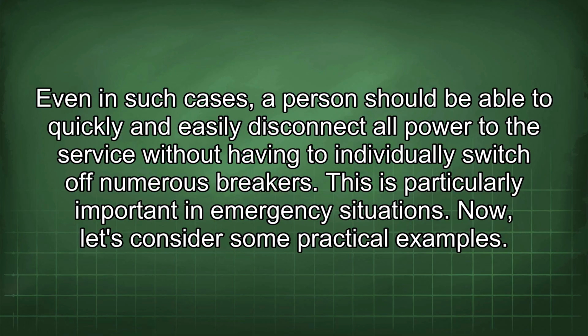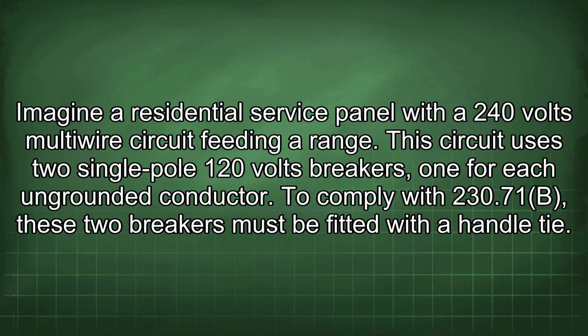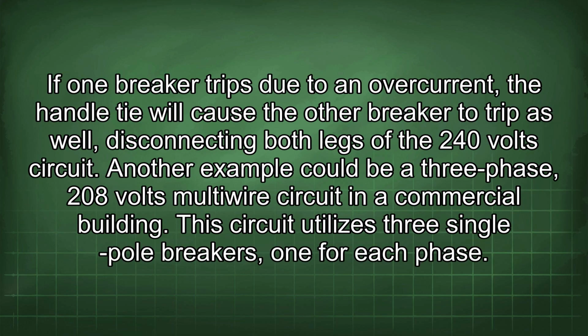Now let's consider some practical examples. Imagine a residential service panel with a 240-volt multi-wire circuit feeding a range. This circuit uses two single-pole 120-volt breakers, one for each ungrounded conductor. To comply with 230.71(B), these two breakers must be fitted with a handle tie. If one breaker trips due to an overcurrent, the handle tie will cause the other breaker to trip as well, disconnecting both legs of the 240-volt circuit.